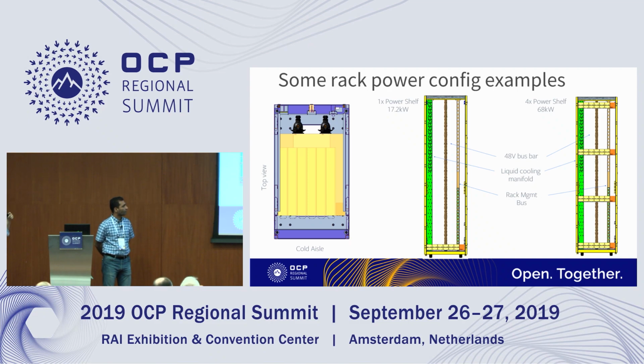We started off with a single power shelf at 17.2 kilowatts because that's dictated by our power cord. Once we started socializing it and looking at the freedom that the 48 volt connector on the back of the tray gave us, one guy came back and said he really wants 4 of these power shelves in a rack. That gets us to 68 kilowatts, which really drives us into needing the liquid cooling manifold.